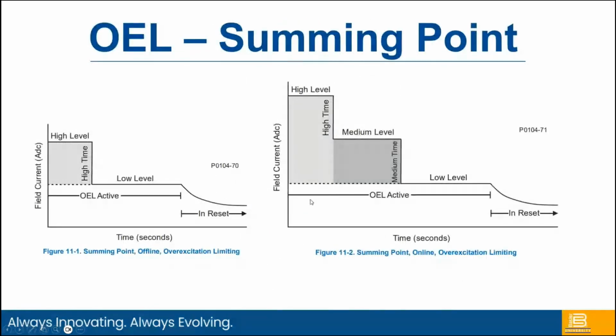The overexcitation limiter, as I was mentioning, has the summing point style, which has an offline and an online, and the difference mainly is the fact that the online has an additional level and time. Anytime that the field current exceeds the low level threshold, the OEL is actually active. It will allow you to continue to operate at that level for the duration of the time delay. After the medium time has expired, it will pull excitation current back down to the low level threshold, where it will allow you to continue to operate until something else occurs. Either you decide to trip offline, or maybe the fault goes away.